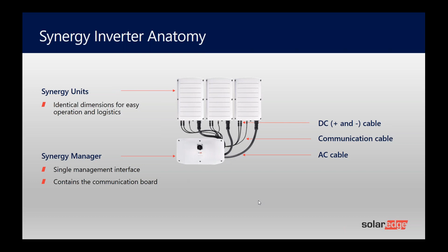So if you're doing larger projects, they're very common on ground mount. If your AC wiring is aluminum, then you have the space now to run aluminum wiring and aluminum lugs. And there's absolutely no reason to go inside the inverter itself, so you can look at that as a sealed unit, with all connections going through the Synergy Manager.